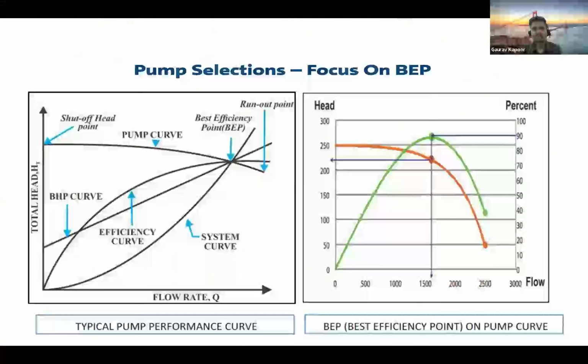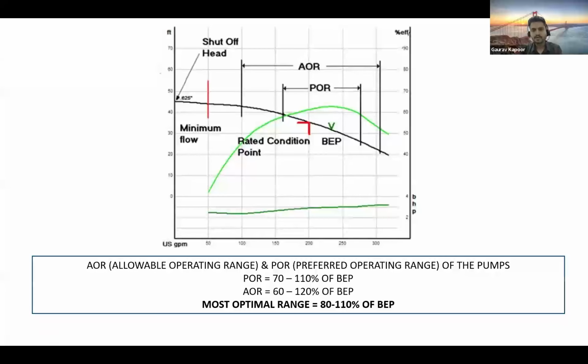Now duty point selection is very important to understand. On the left side you see a curve, which is a pump curve, and then you have a parabola efficiency curve. BEP, as I just informed, is the best efficiency point. It is the point where the pump delivers the maximum efficiency, meaning it will consume the lowest kilowatts to deliver that particular flow and head. And this is very important to understand, because at that point your flow forces, vibrations and noise are the lowest.